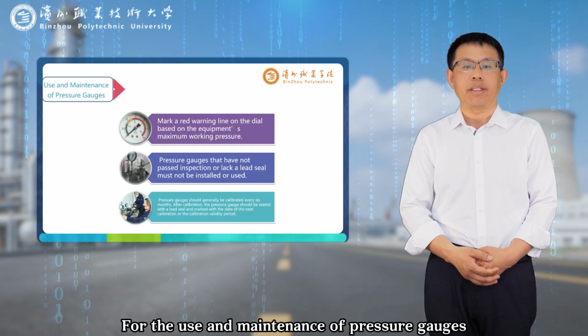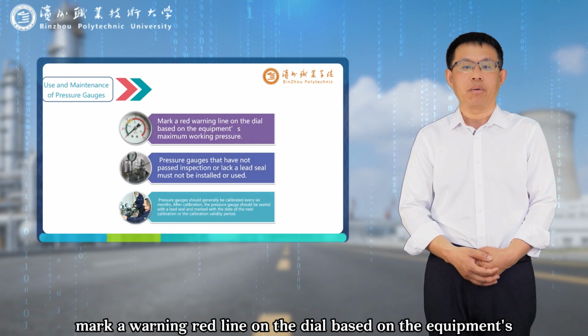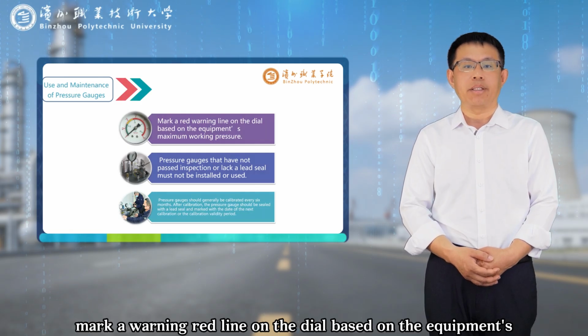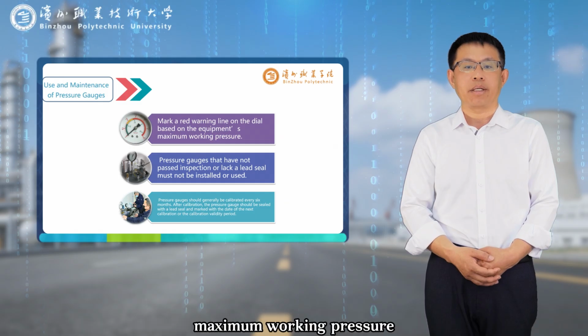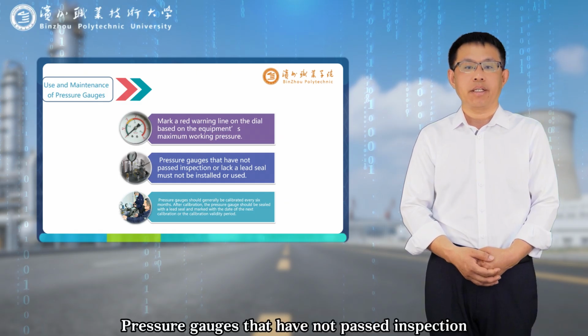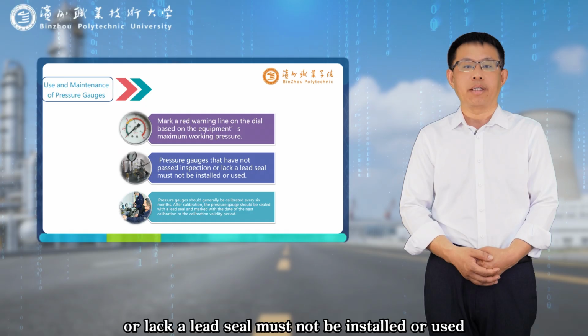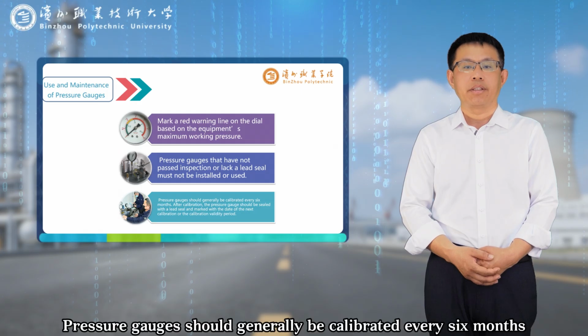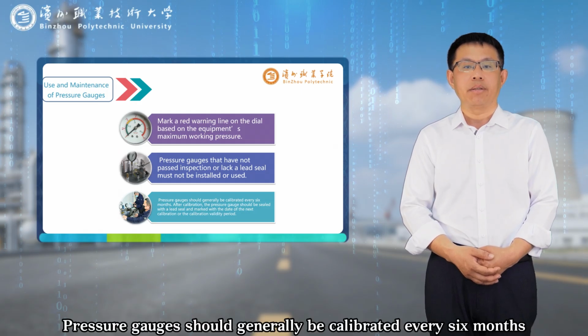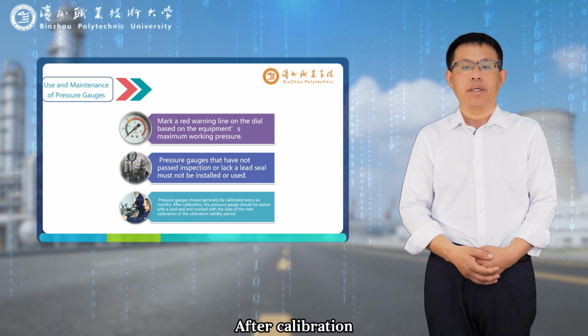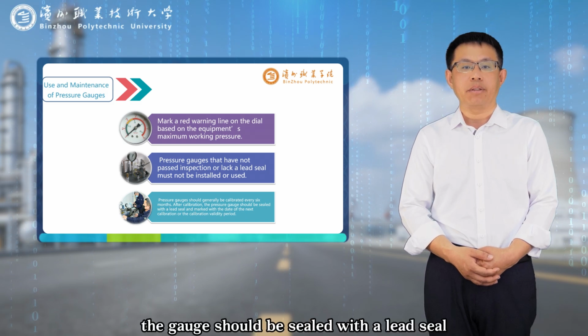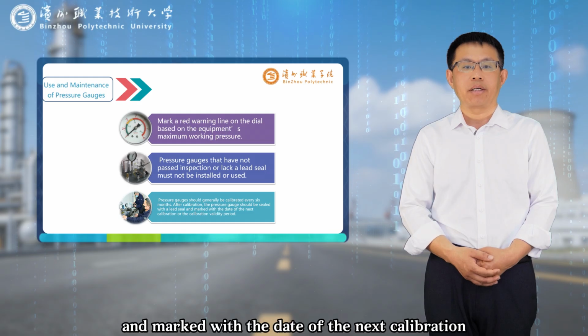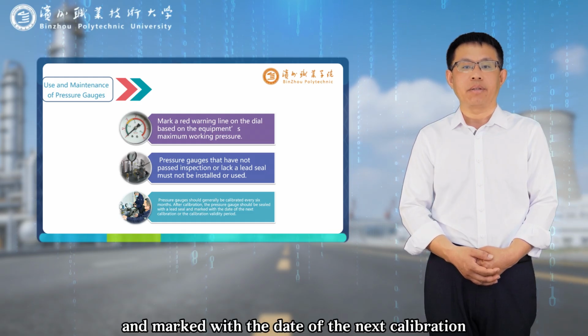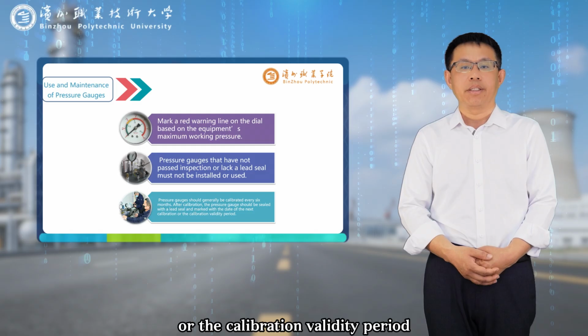For the use and maintenance of pressure gauges, mark a warning red line on the dial based on the equipment's maximum working pressure. Pressure gauges that have not passed inspection or lack a lead seal must not be installed or used. Pressure gauges should generally be calibrated every 6 months. After calibration, the gauge should be sealed with a lead seal and marked with the date of the next calibration or the calibration validity period.